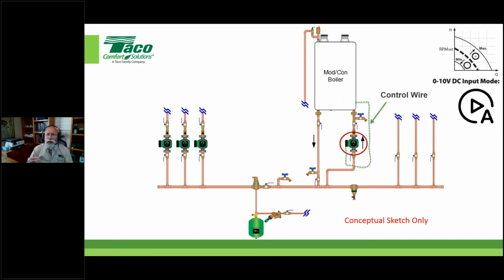The only issue is, Taco makes circulators in the mid-range size and the light commercial size that have 0 to 10 technology. Most everybody, including us, their small pumps are little tiny pumps. In our world, it's a little 44-watt circulator that currently doesn't have, in an ECM offering, the ability to have that 0 to 10. So my next slide will tell you why we're still talking about things. Otherwise, we would just say, always do this.